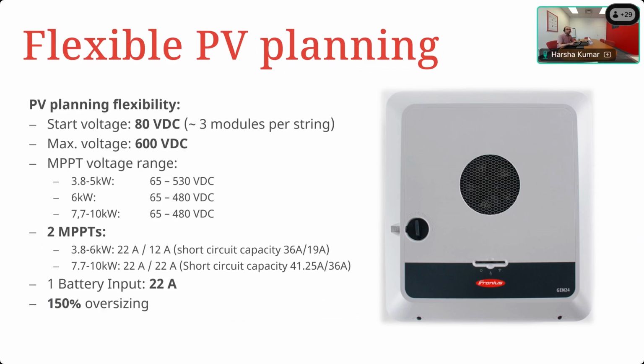In addition to this, we also allow for oversizing, and the maximum permissible oversizing without voiding the warranty is 150%. What I mean by oversizing is the size of the PV array in watts or kilowatts connected to a particular size of inverter, and the ratio between the inverter's AC output versus the DC input connected to said inverter. So for example, if I have a 10 kilowatt inverter that I'm thinking about, the maximum permissible DC array size that can be connected to this inverter, making sure that the current and voltage are still within limits, is 1.5 times the inverter's rated AC capacity, which means for a 10 kilowatt inverter, I can connect a 15 kilowatt PV array.